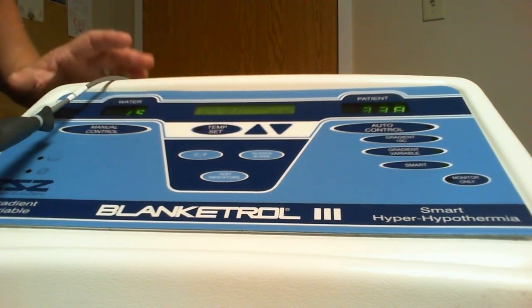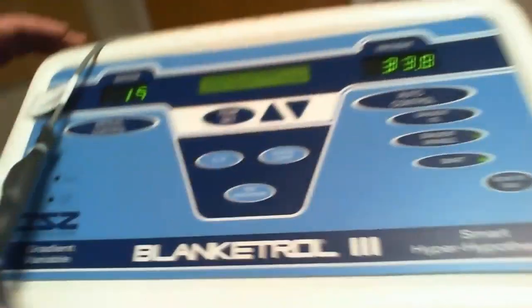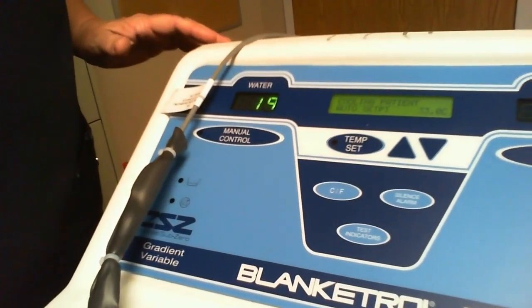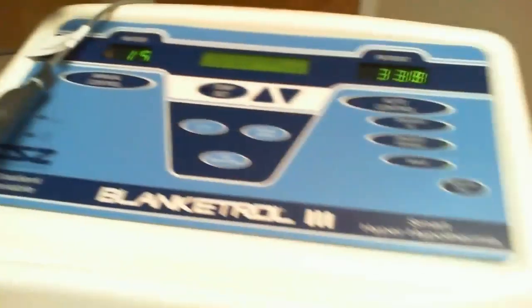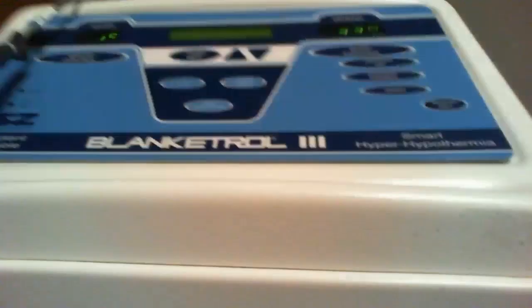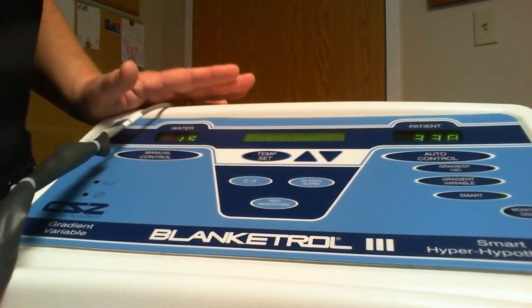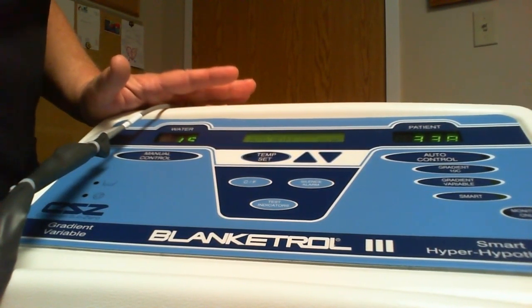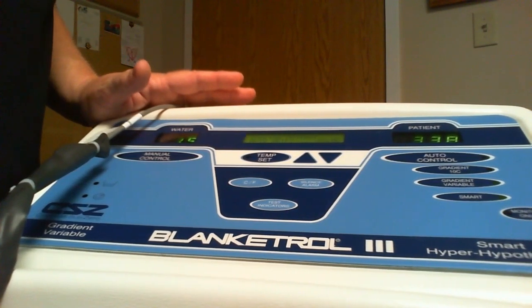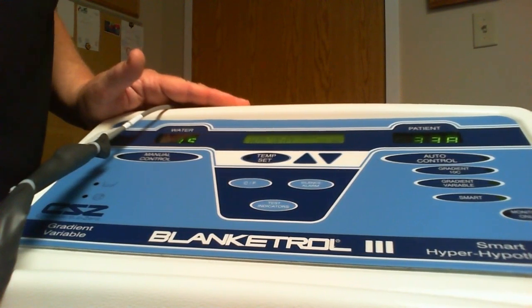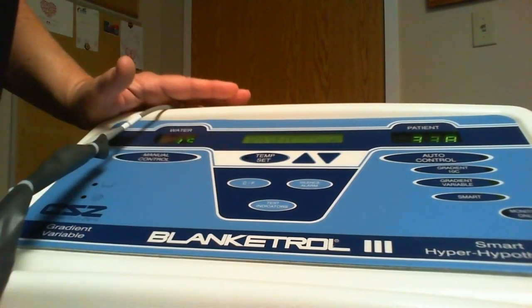You'll see that the water temperature when we first started out was at 25 degrees. Temperature has significantly dropped, and now the temperature of the water here is 19 degrees. And so that is really all there is to using this blanket. It is sometimes a trial and error. It is very non-invasive. The material that the disposable blankets are made of is really quite lovely. You do not need a sheet between the patient and the disposable blankets.